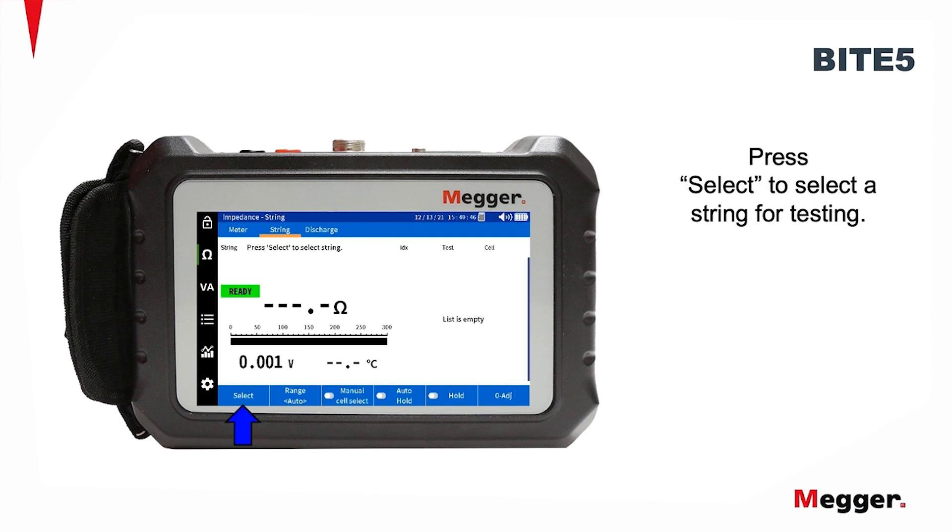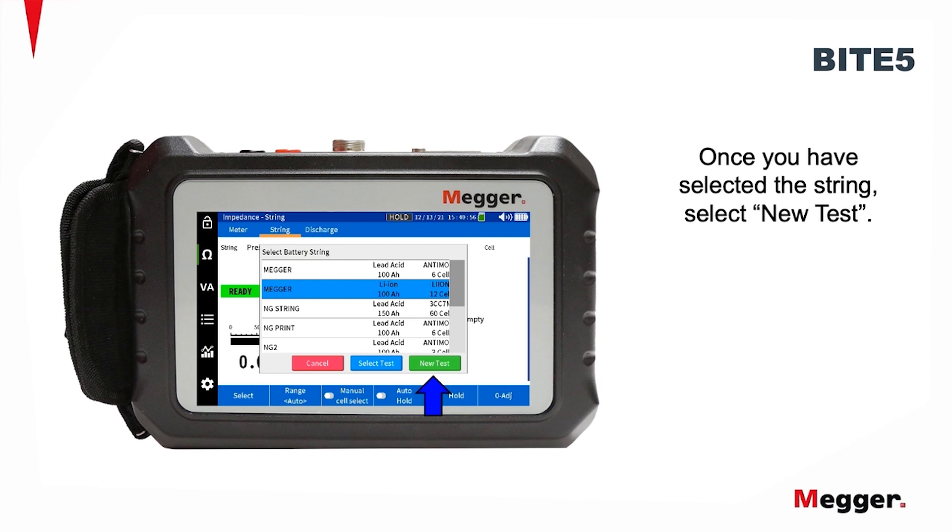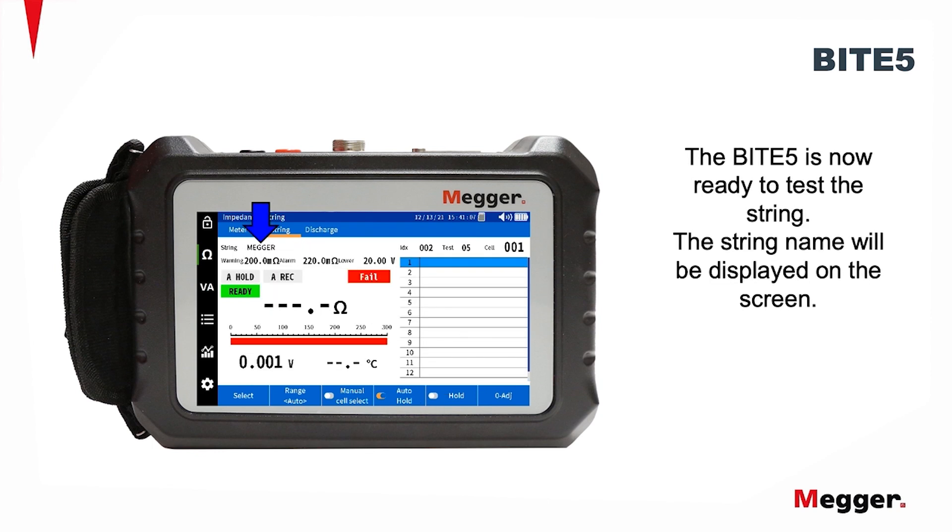Press Select to select the string for testing. Select the desired string to test. If the string is not present, please view the string configuration video. Once you have selected the string, select New Test. The BITE5 is now ready to test the string.